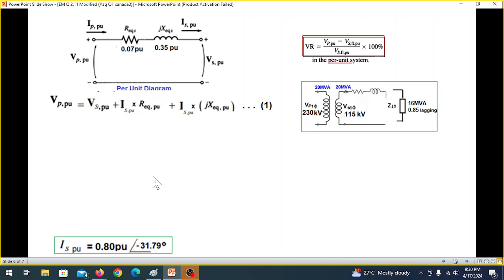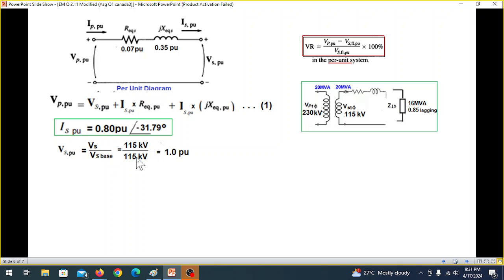So we were here, we have calculated ISPU, and we can plug in, but we don't know what is VSPU. Now, the best method is that, look here, the rated voltage is always the base voltage. So the base voltage is 115, and the actual voltage here is also 115. So 115 divided by 115, it is 1.0 PU. Also, we can use the diagram, and here we take this as 1, because we are taking as reference, and all measurements are based on this reference, therefore, we can write it as 1.0. Whichever method you like, I think this is a better method.